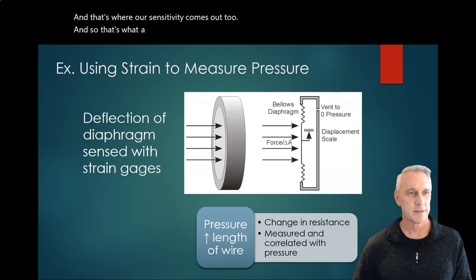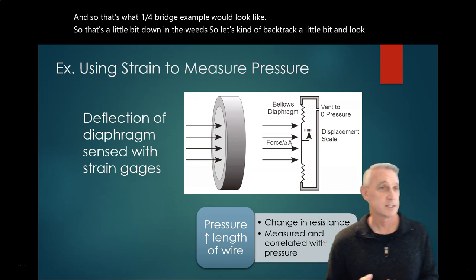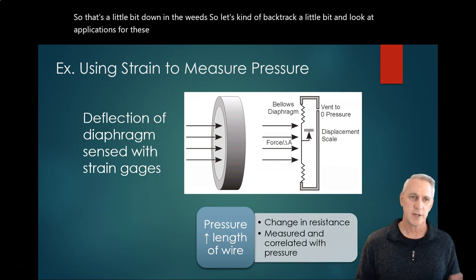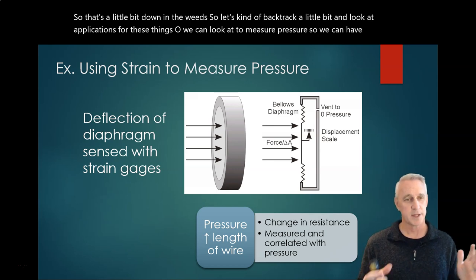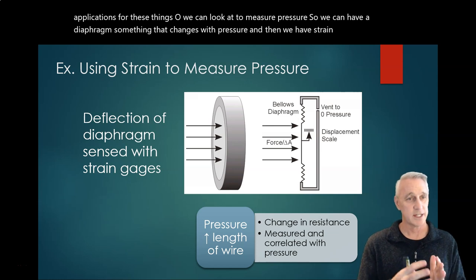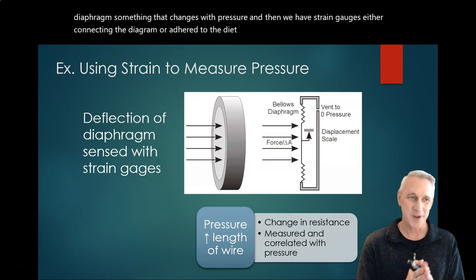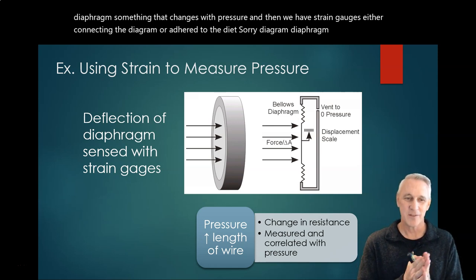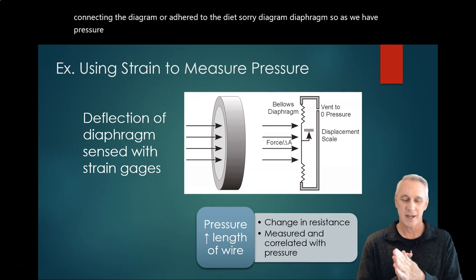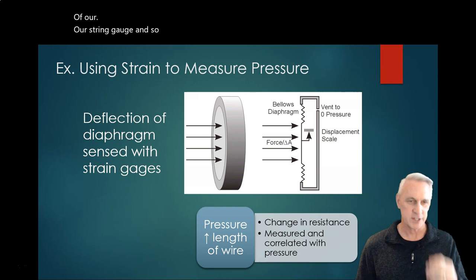So that's a little bit down in the weeds. So let's backtrack a little bit and look at applications for these things. So we can look at strain to measure pressure. So we can have a diaphragm, something that changes with pressure. And then we have strain gauges either connecting the diaphragm or adhered to the diaphragm. So as we have pressure increasing, we get an increased stretch of our strain gauge. And so our displacement goes up, we can measure that.